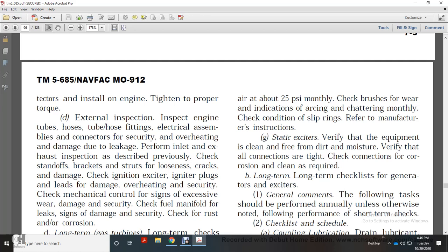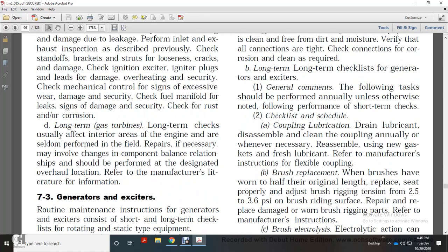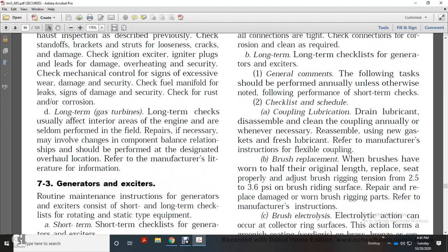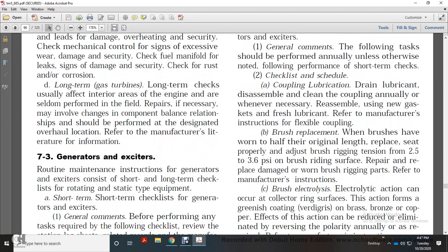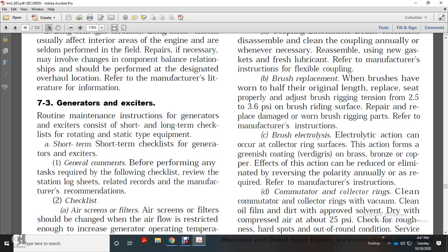Long-term checklist for the generator exciter. General comment: the following tasks should be performed annually, unless otherwise found with the performance of the short-term checklist, and scheduled coupling lubrication drain lubricant, disassemble. Clean the coupling annually whenever necessary. Reassemble with a new gasket and fresh lubricant, referring to manufacturer instruction for the flex coupling. Brush replacement: replace brushes that have worn to half of the original length, and seat them properly. Adjust the brush spring pressure within 2.5 to 3.6 psi on the brush rigging surface. Repair or replace damaged or worn brush rigging parts, referring to manufacturer instruction.